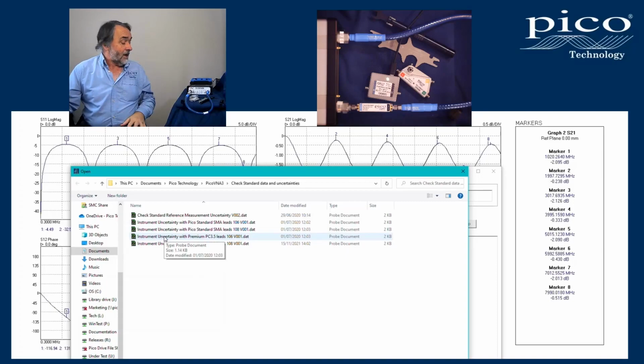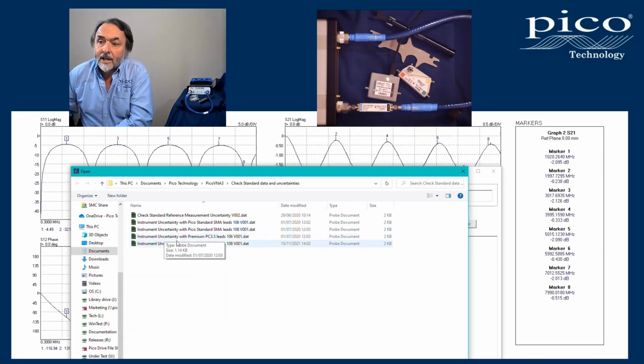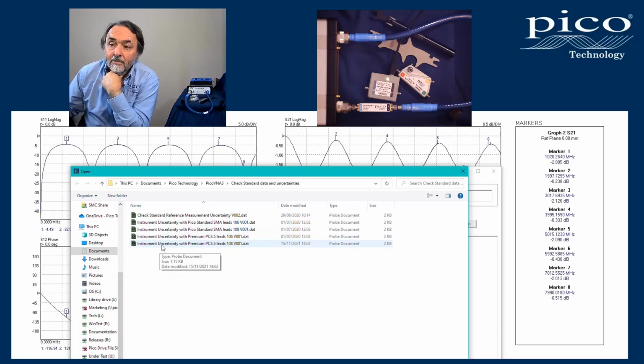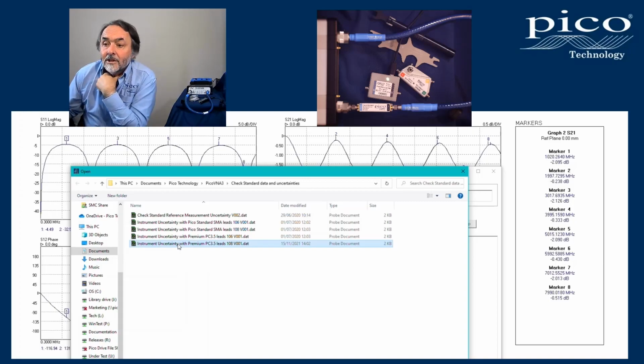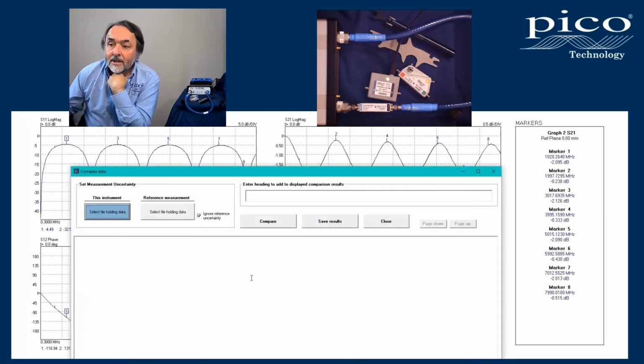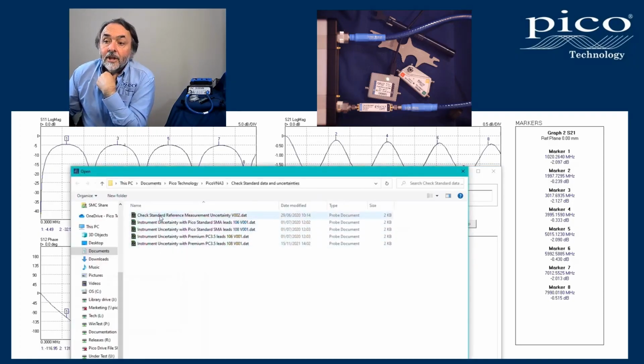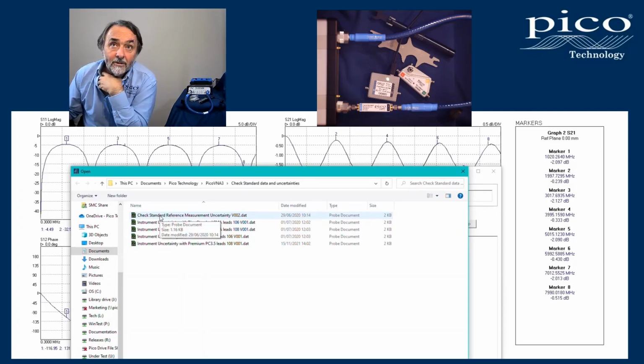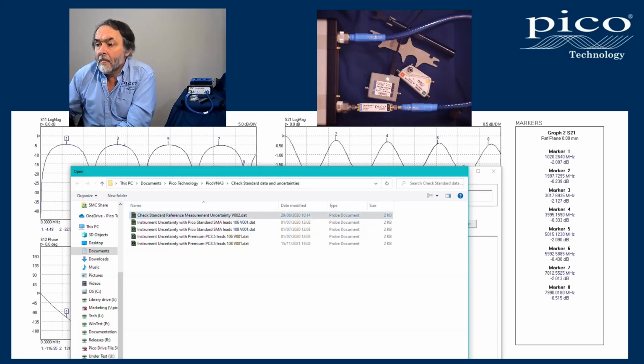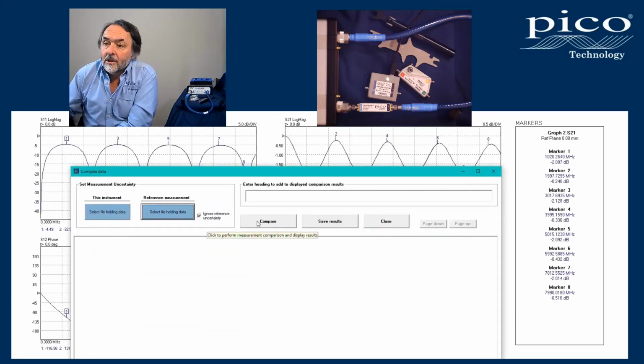But I am very happy that these are very high quality SMAs, and I want to show you the performance to the best degree I can. So here we go. I'm going to use this uncertainty, which is the tightest. So we'll open that, and we're also going to open the uncertainty of the reference for the measurement of the check standard. And this is done in a first tier arrangement, directly traceable to the National Physical Laboratory. So that data came with the check standard. Open, and we're going to compare.